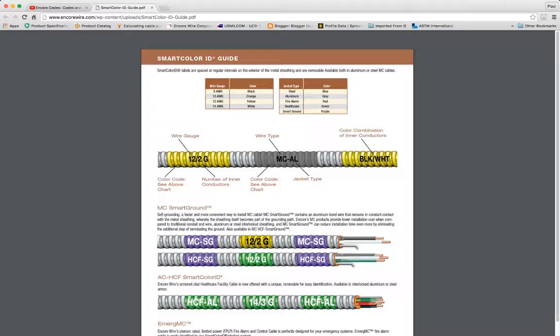So it's a 12-2. It's got a black and a white and a ground. Now the ground in most of these branch circuit type cables are going to be green. The code allowed, the National Electrical Code in 250.118, allows the equipment grounding conductor to be bare, covered, or insulated.